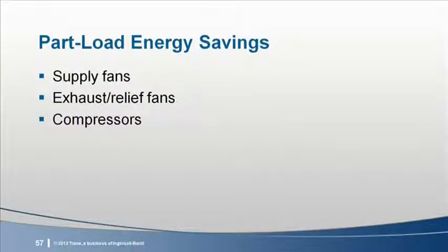Sure. We now know that SingleZone VAV systems are suitable for spaces that have varied cooling load profiles. These reduced cooling loads present opportunities for part load energy savings with respect to the supply fan, exhaust or relief fan, and compressors. As the cooling load decreases, the fan motor can reduce its speed and airflow. In addition to reduced electrical demand, the compressors respond by cycling, reducing speed, or any other unloading method. This also allows for additional energy savings compared to a traditional constant volume system. Validating potential energy savings with an energy modeling program, such as TRACE 700, can be considered.